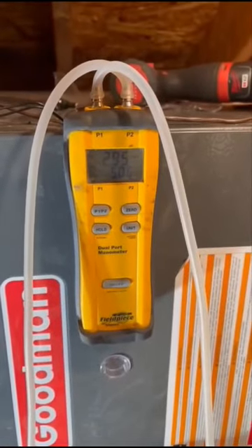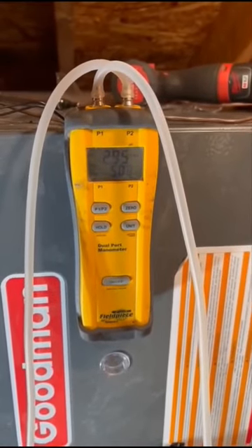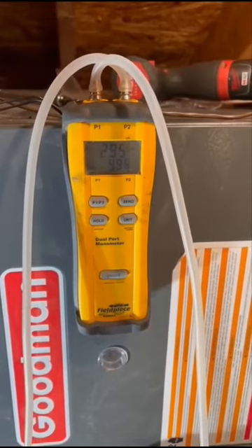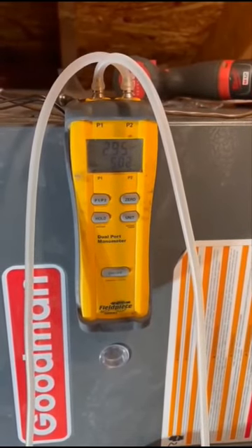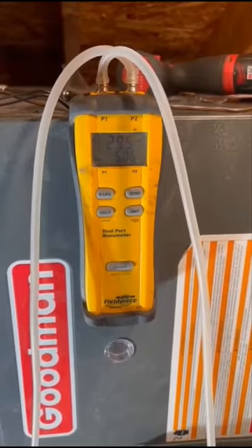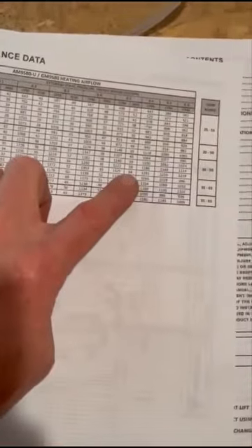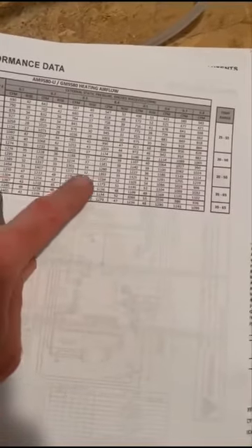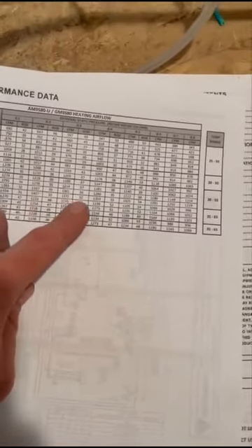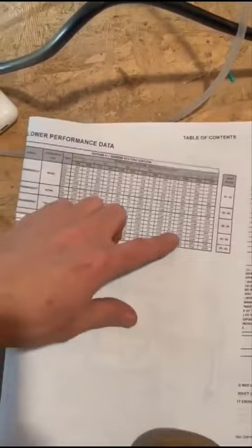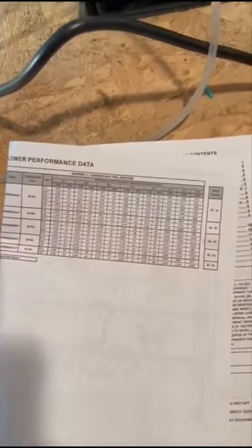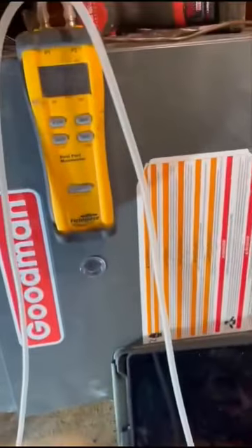Okay, so we're running 10 minutes. As you can see, incoming pressure is 5 inches of water column. The pressure after the valve, after I adjusted it, is 2.95 inches of water column. Then we're running on tap 5, and our heat rise right now, I'm just looking at my Job Link Pro. My iPad just turned off, but I'll send you a screenshot. That's 30-degree heat rise. So we're right within the range of 20 to 50 degree difference between the supply and the return. So commissioning is done.